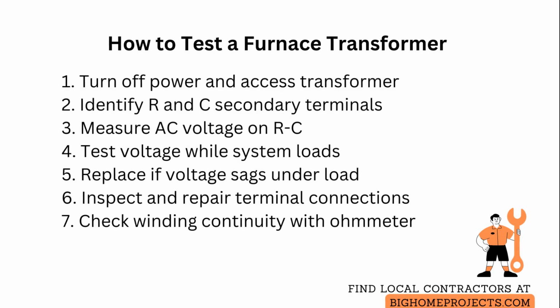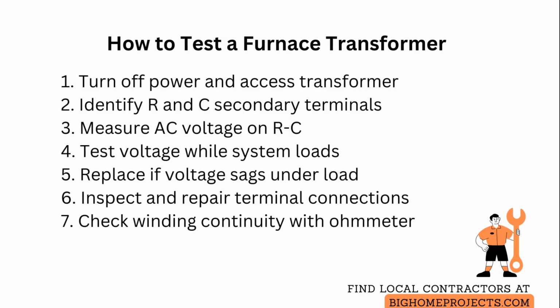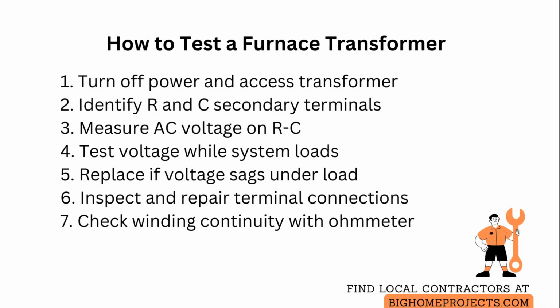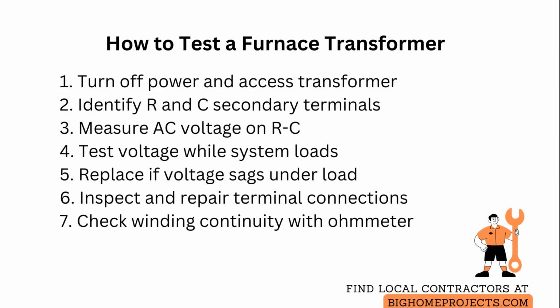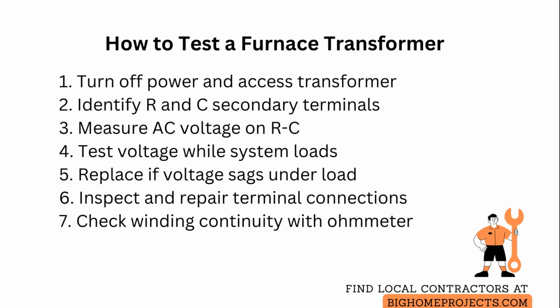For intermittent faults, wiggle the transformer connections and inspect terminals for corrosion, looseness, or heat discoloration, and replace any compromised connectors or wiring. Use crimped ring terminals and heat shrink tubing for reliable, service-grade splices. If the secondary measures open circuit, verify continuity through the transformer windings with the meter on the ohm setting. No continuity means an internal winding failure and replacement is required.